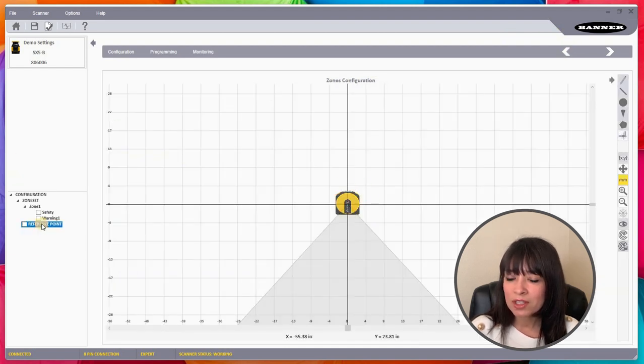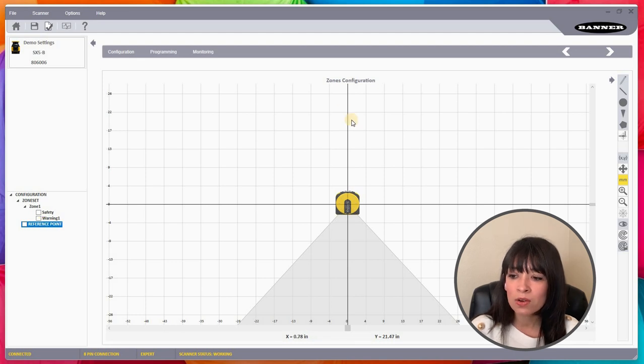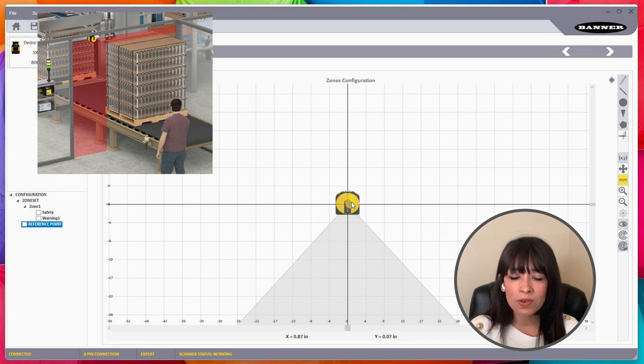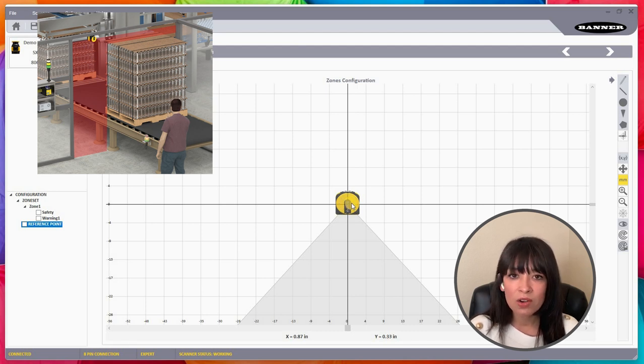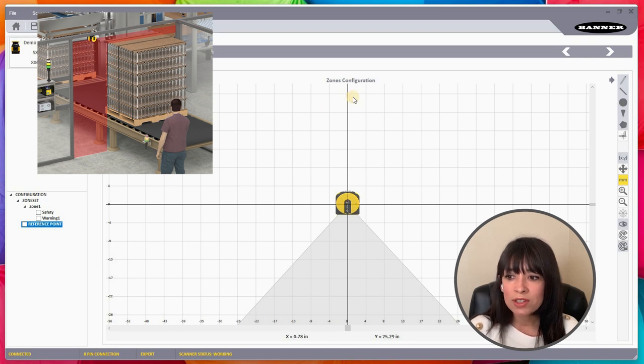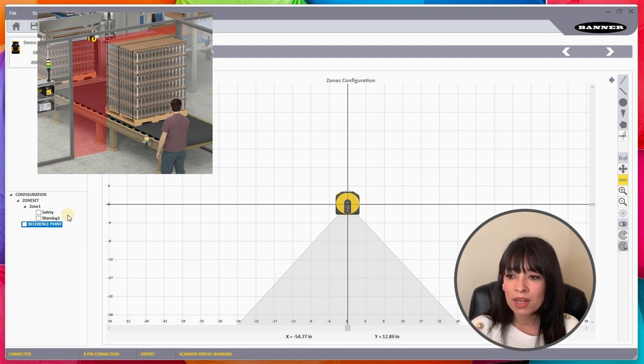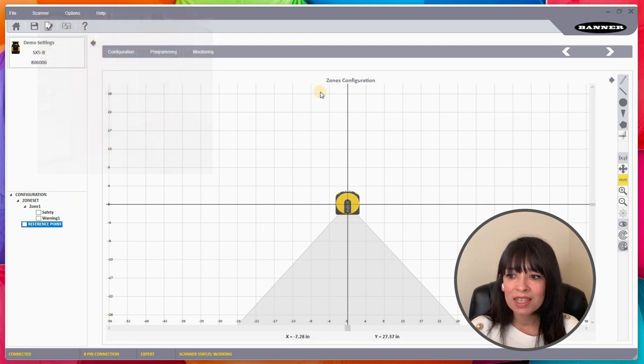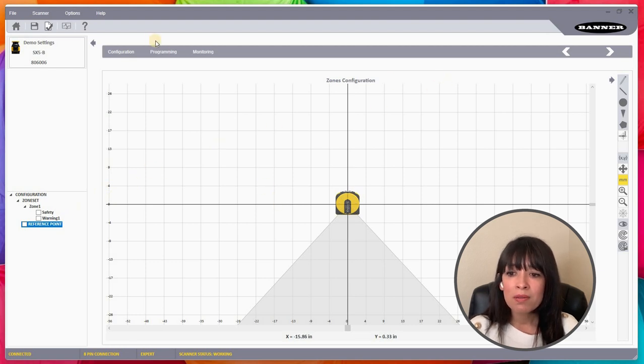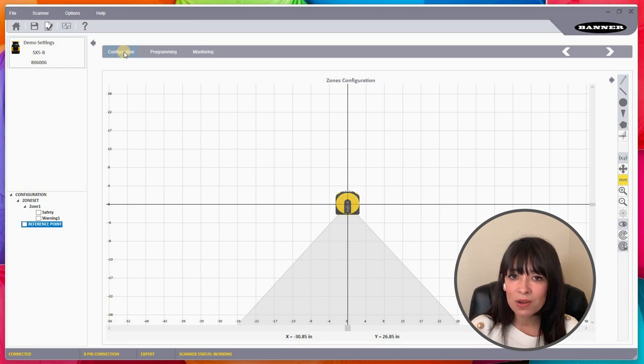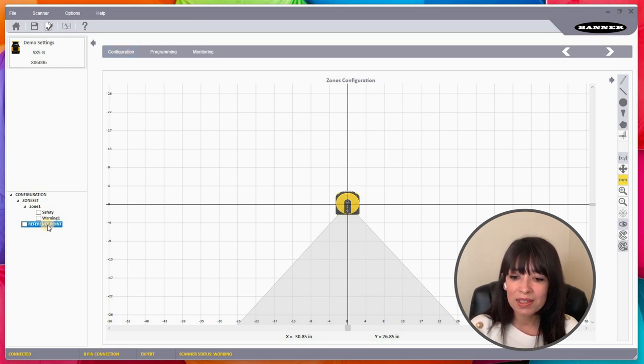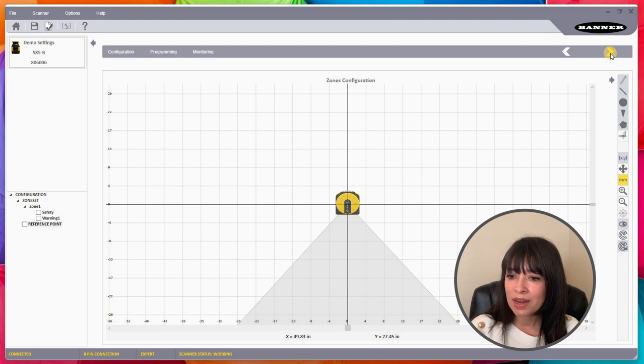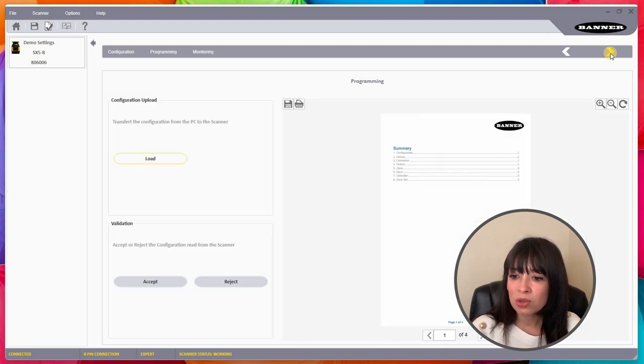I'll just go ahead and click the next button. I forgot to mention the reference point. The reference point is there in case you're facing this down vertically in a vertical application. You need a reference point so if the safety scanner falls or it loses its reference point, maybe there's a lot of vibration in the area or something becomes dislodged, the reference point you can have it set there so that this point will always be there. That's also really helpful. If when you begin the program you had it set for vertical applications, this won't let you advance unless you mark your reference point. I thought that was also worth mentioning.